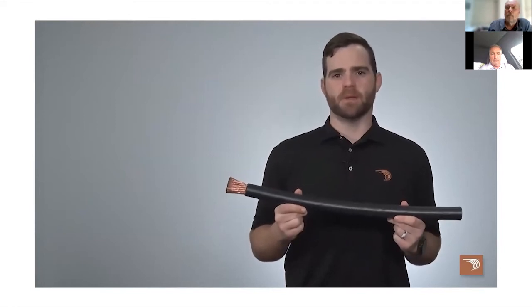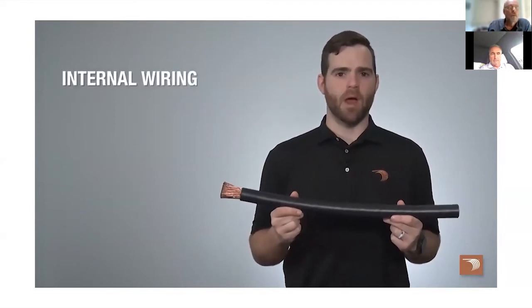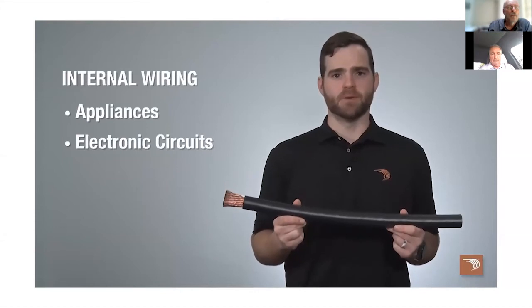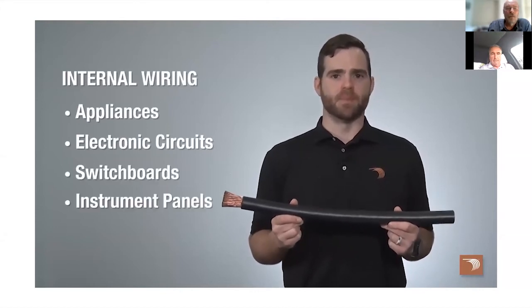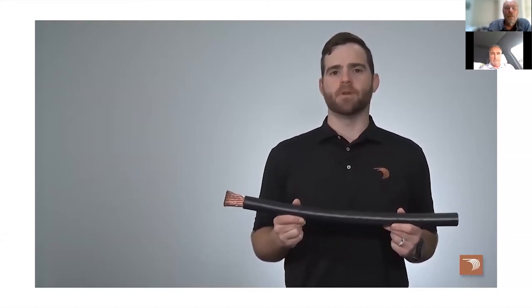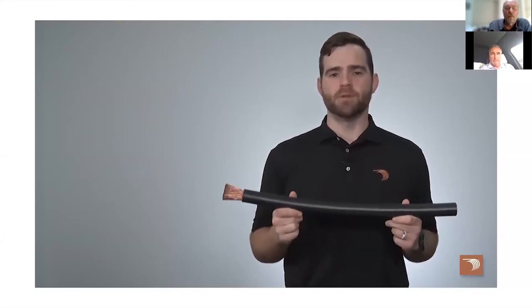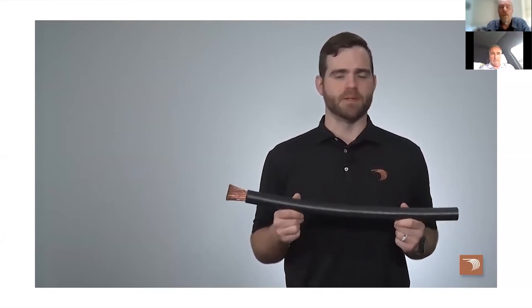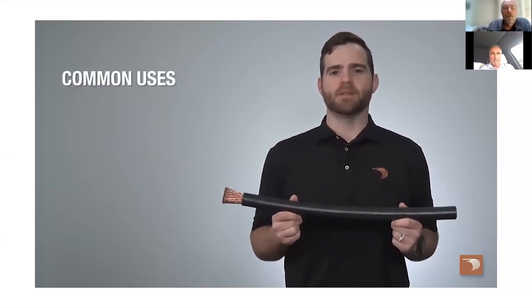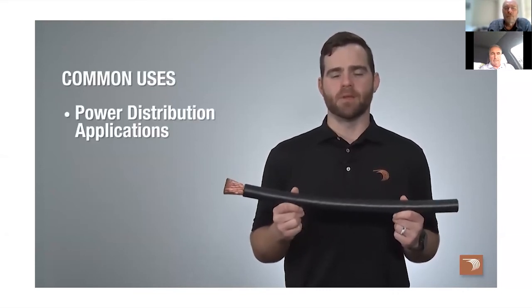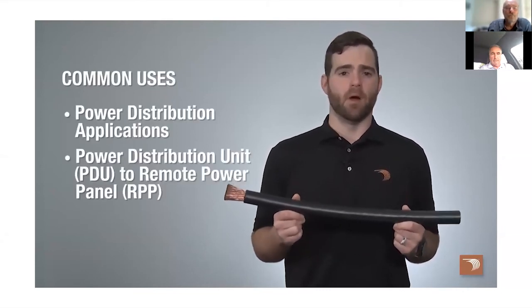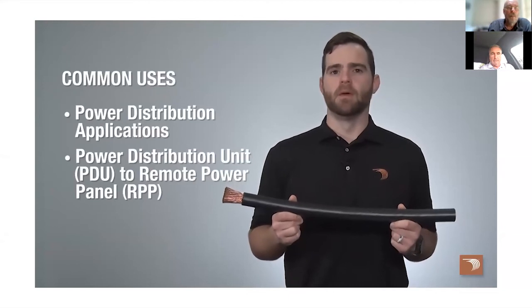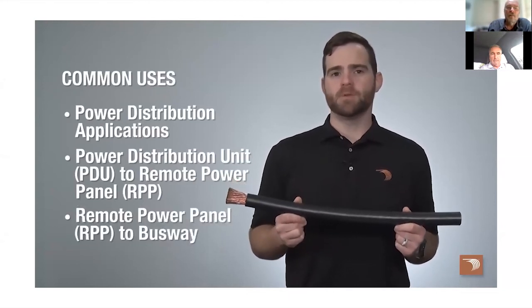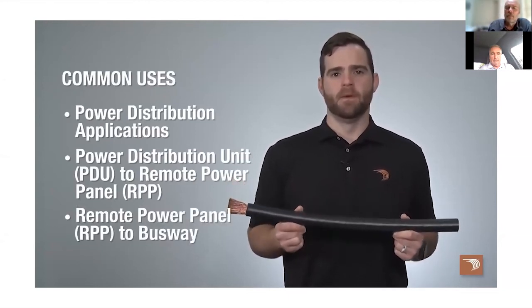It's permitted for 600 volt applications and can be used for internal wiring of appliances, electronic circuits, switchboards, and instrument panels. FlexCore is optimal for use in data center applications where reduced bending radii and tight workspaces may be present. Common data center uses include power distribution applications between a PDU, or power distribution unit, and RPP, remote power panel, as well as between the RPP and busway.